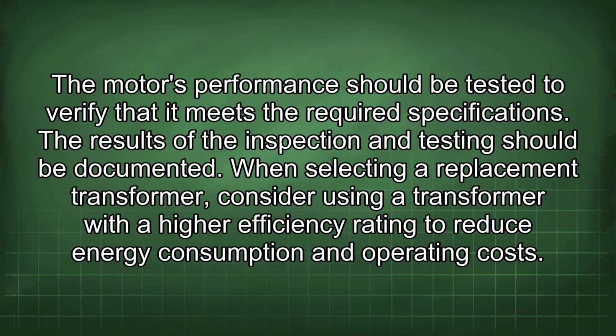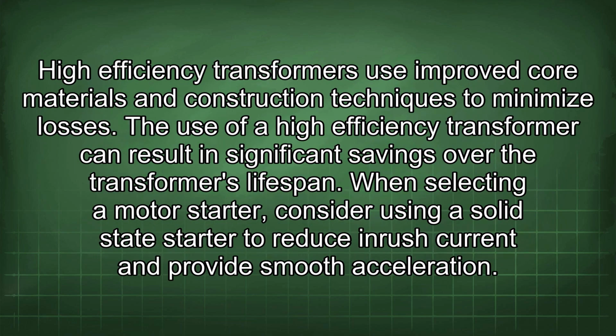When selecting a replacement transformer, consider using a transformer with a higher efficiency rating to reduce energy consumption and operating costs. High-efficiency transformers use improved core materials and construction techniques to minimize losses. The use of a high-efficiency transformer can result in significant savings over the transformer's lifespan.